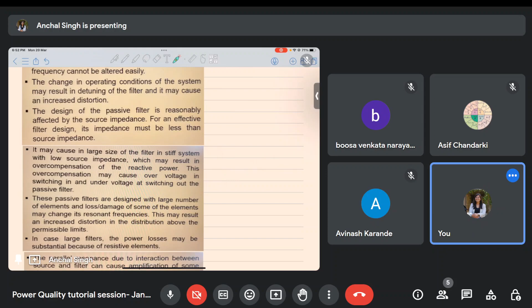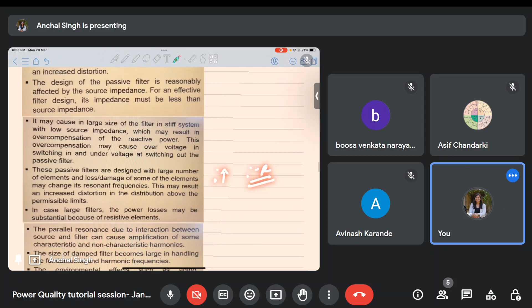Then another one is these filters are designed with a large number of elements, right? We have seen so many elements, separately for third harmonic, for fifth harmonic, seventh harmonic, then high pass filter. So many elements we are putting. So when these passive elements are present in the circuit, they have their own individual losses, right? And then they might lead to resonance, which has very high current, which means very high I square R losses. So these losses have to be taken into picture. Then parallel resonance problem might occur, which might lead to additional power quality problems. When resonance occurs, then there might be different kinds of non-characteristic or characteristic harmonics present in the system. And due to the heavy current, my breaker or protection circuit might get damaged. There might be a lot of other problems.